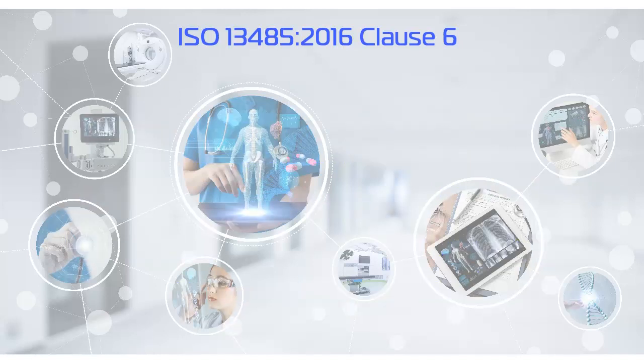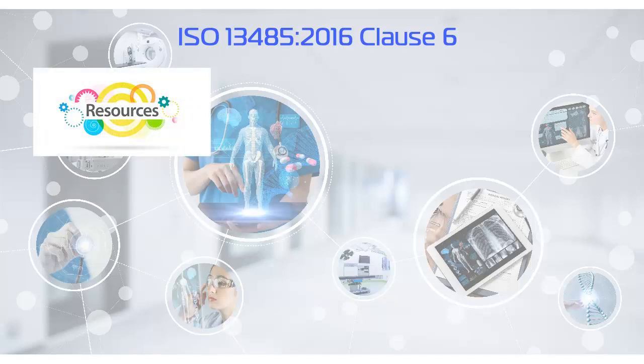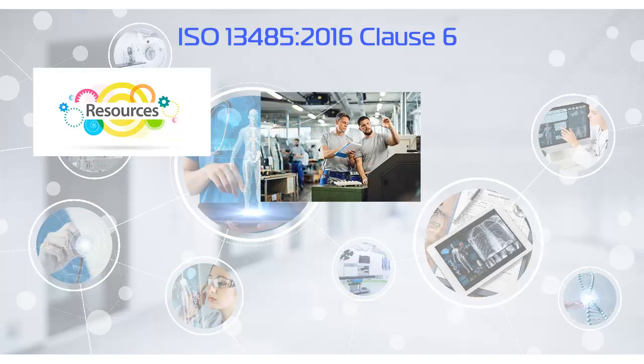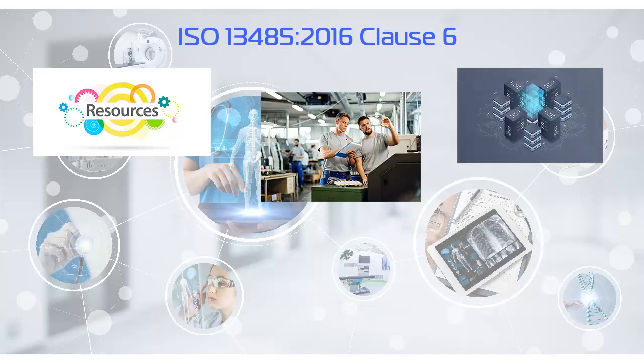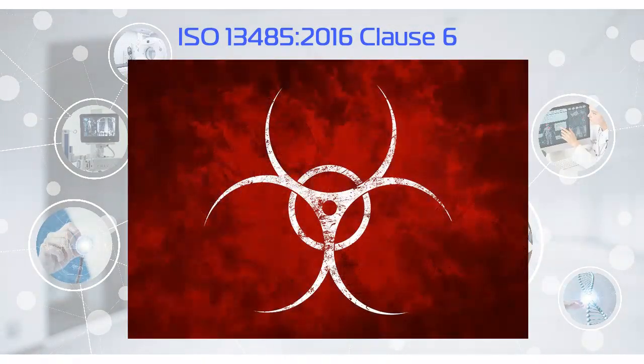Clause 6 sets out the requirement to provide the resource that is necessary for an effective QMS. You have to identify the people in the jobs affecting product quality and ensure that these people are competent. You have to provide the infrastructure and the work environment needed to ensure medical device safety and performance, such as health, cleanliness, and clothing requirements. Where these could affect product quality, you have to establish arrangements to prevent contamination.